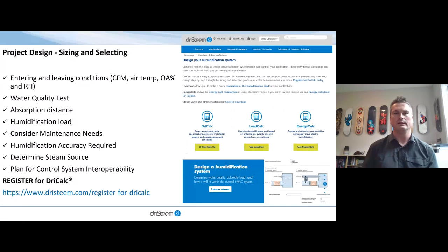Also, the water quality, understanding what the water quality is that we're working with. The absorption distances available, whether that's in a ducted system or an air handler. How much distance do we really have to work with? And we also need to take into consideration, which I won't discuss in this presentation, elbows, transitions, sizing changes, things like that in the airflow. Those are all important factors to consider and understand when laying out a humidification system.